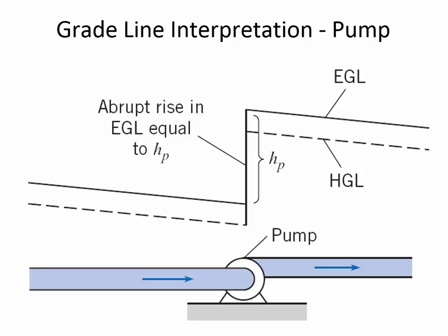It's going to be going from tank to tank very slowly. But as soon as we kick that pump on, and the pump adds a lot more energy in the form of pressure, then the water is going to be moving faster. Because if the pump is adding, let's say that this elevation is 10 meters, and this elevation is 3 meters. So right now there's a 7-meter energy differential that's driving the flow.